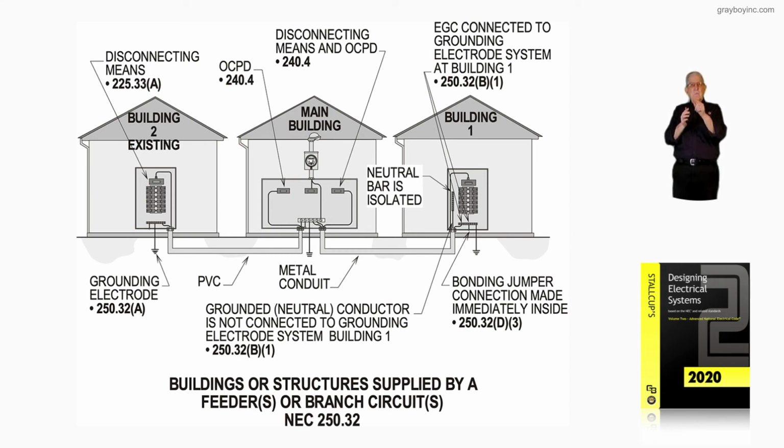Then you would need a number 2 to serve as a path for an effective ground fault path if you didn't have an overcurrent device. But you have an overcurrent device ahead of it, so it would be based on 225 amp, it'd be a number 4 run over there. You could say, okay, I have a number 4, that serves as an effective path for the ground fault. It also serves as a bonding means to bond the metal in the building number 2 enclosure back to the main panel board in the main building.